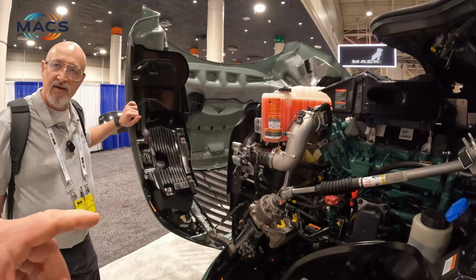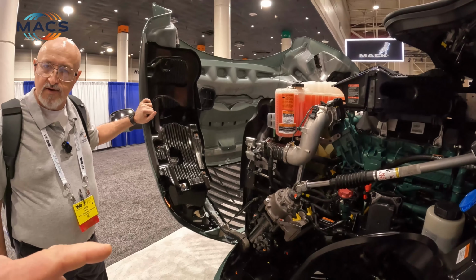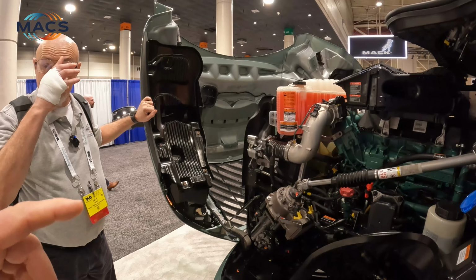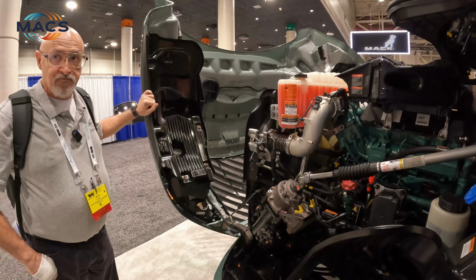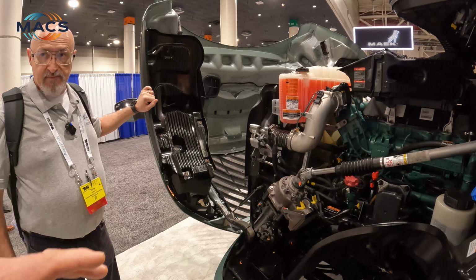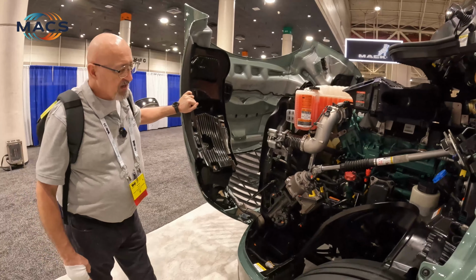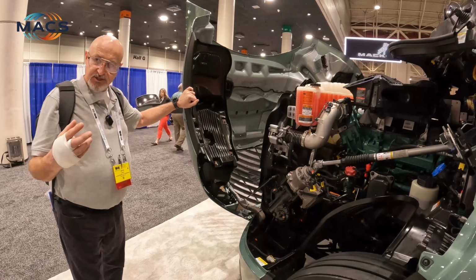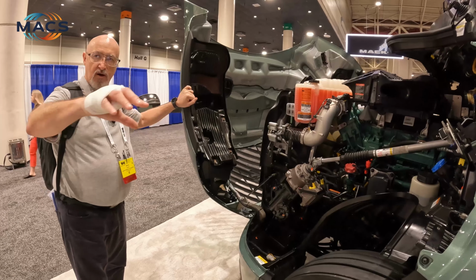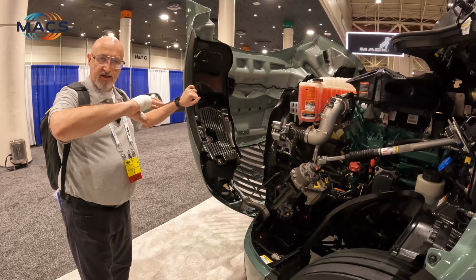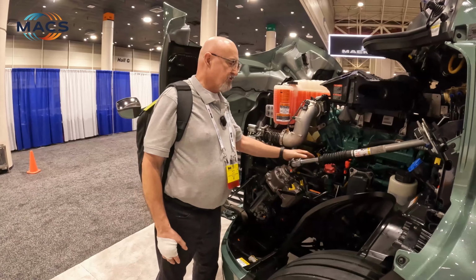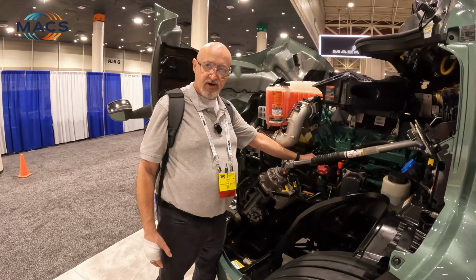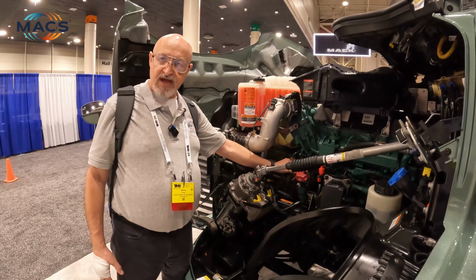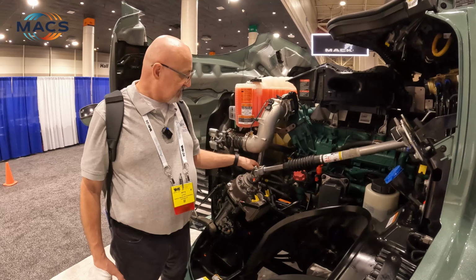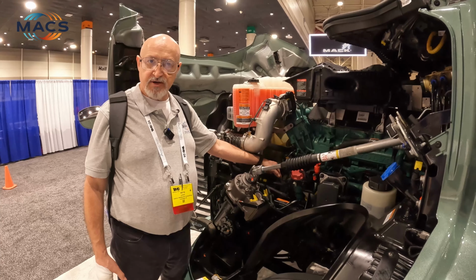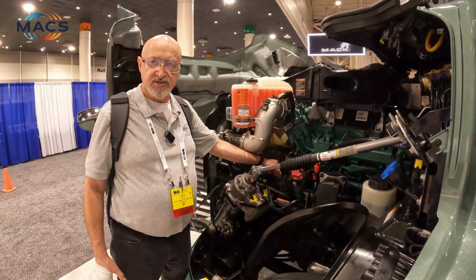Okay, so the two valves are on the discharge lines of each compressor. Correct. So if you close it off, aren't you trapping refrigerant between the compressor and the valve? There may be some trapped there, but more likely what will happen is when you're doing the suction scavenge, you'll pull all the gas out of both suction lines until there's basically ambient pressure in the suction line being drawn by the other compressor. You may get some backflow through that compressor in order to balance, but even if there's only a little bit of gas trapped under pressure, it's not going to be material to the performance of the AC system.